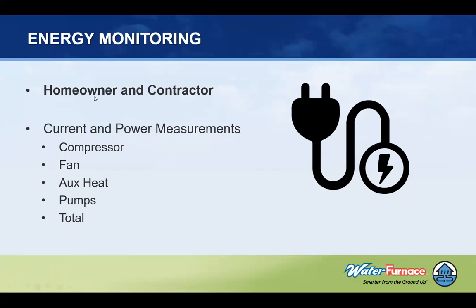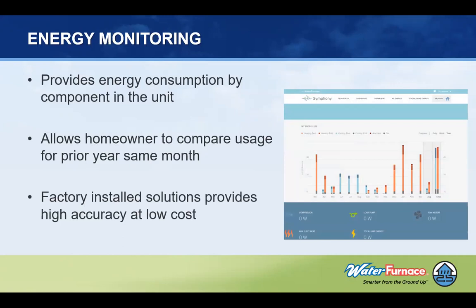So energy is available to the homeowner and to the contractor, and it provides the current and power measurements for the compressor, the fan, auxiliary heat, and the pumps, and then it provides a total energy consumption on an ongoing basis. From energy, you can see the consumption. It can compare your usage from the prior year to the same month. So in this example, we have March of this year on the right, March of last year on the left, and it allows you to have a rolling 13 months of your energy consumption so that you can see what's going on.